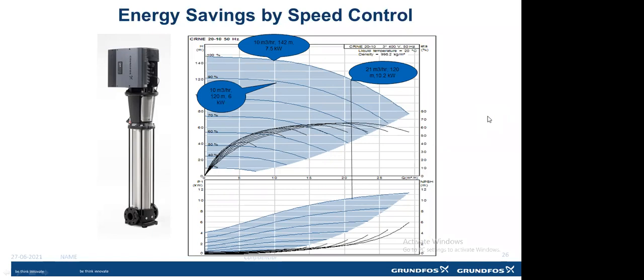As per demand, actually, it's not recommended. But we'll take 2 cases here. First one is with a constant flow, and if there is a constant flow, we can straight away go for impeller trimming, and we can reduce the head for that pump. But at the same time, check how much the flow is also reducing with the impeller trimming. And if it is a variable flow requirement, then it's always recommended to go for the VFD. So it depends on how your flow requirement is, whether it is constant or variable. So accordingly, we need to take a call.